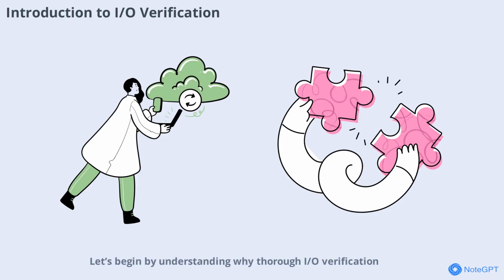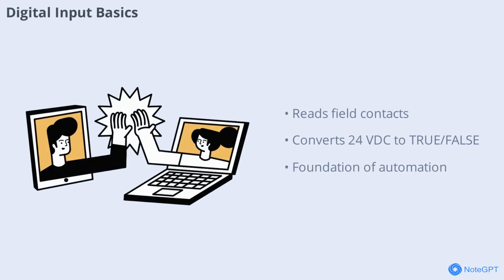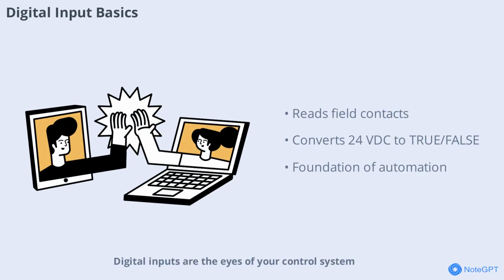Let's begin by understanding why thorough I/O verification is critical for successful commissioning and safe operation. Digital inputs are the eyes of your control system, reading the state of field contacts like limit switches, push buttons, or motor feedbacks. These devices convert 24 VDC signals into true or false values, forming the backbone of automated decision-making. Understanding how digital inputs work is essential for accurate system operation. In this scene, we'll explore how these signals are processed and why their reliability is vital for both safety and performance. Let's see how digital input verification starts the journey from field device to control logic.